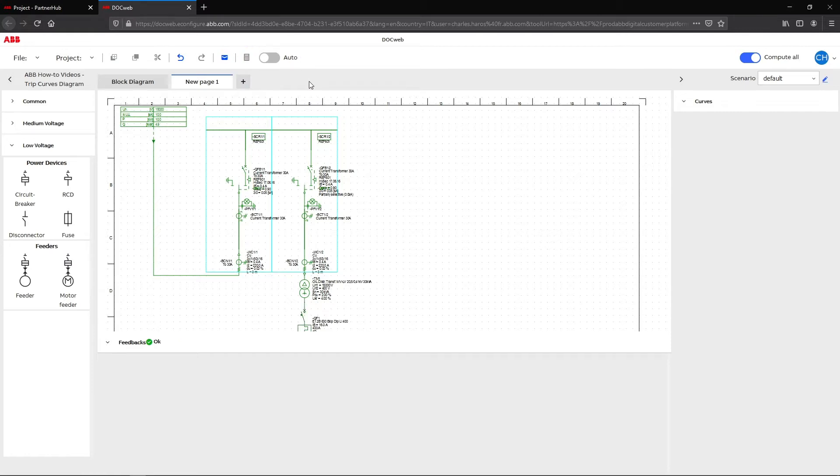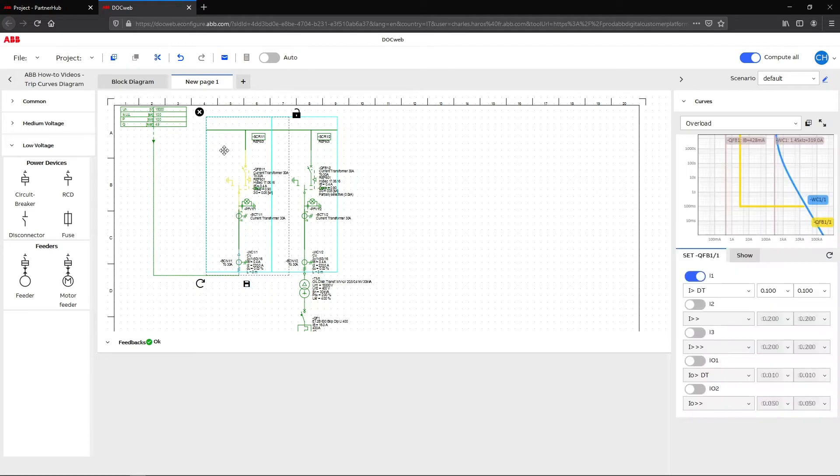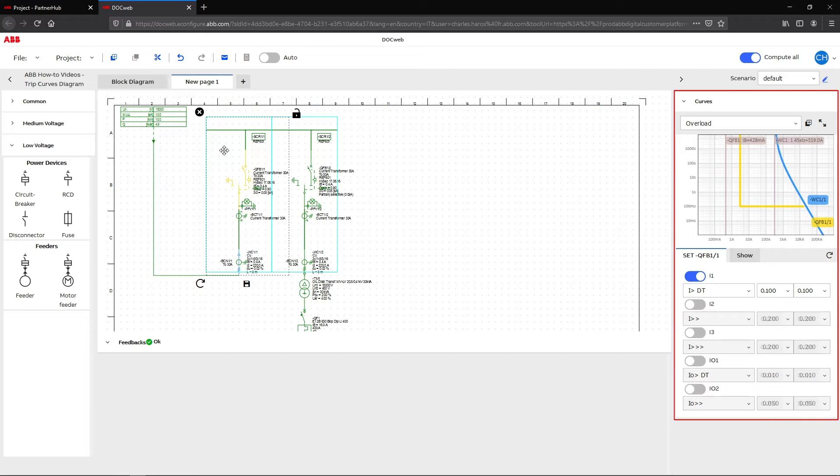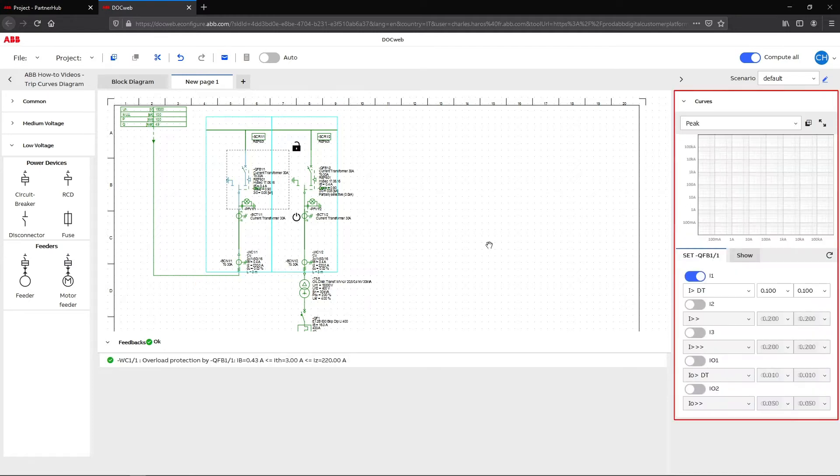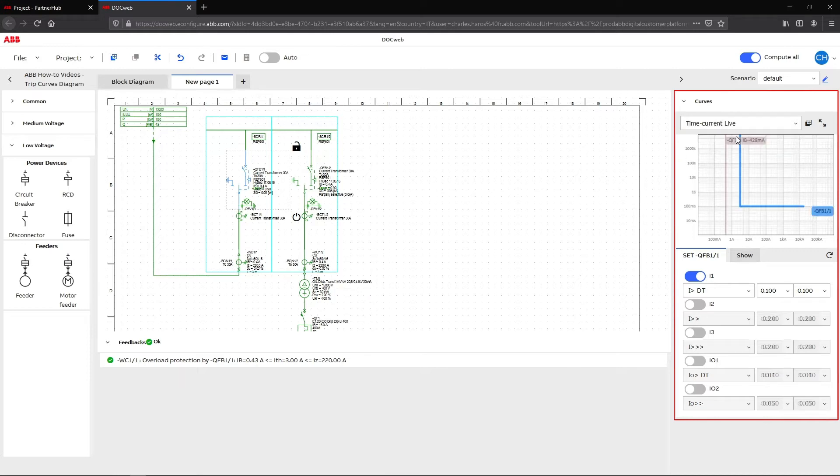After this operation, the curves section is now accessible in the right column in DOCweb. Trip curves are available for each panel equipped with relays or fuses. To open the curves section, you must select an element. For a macro computation of the protection curve, select the entire panel.